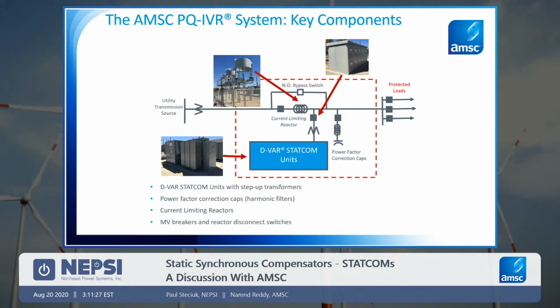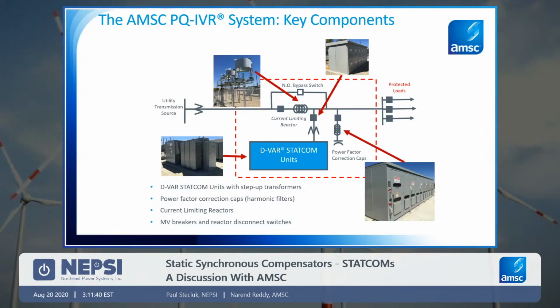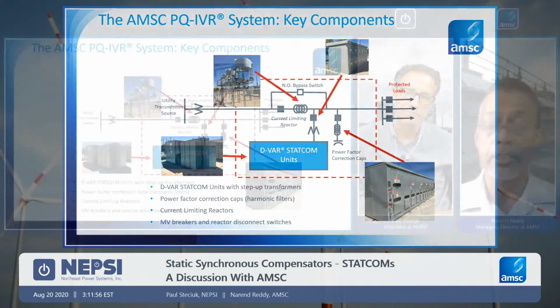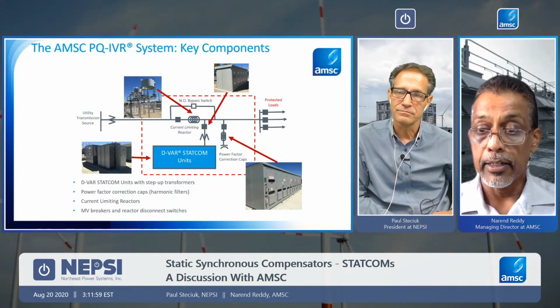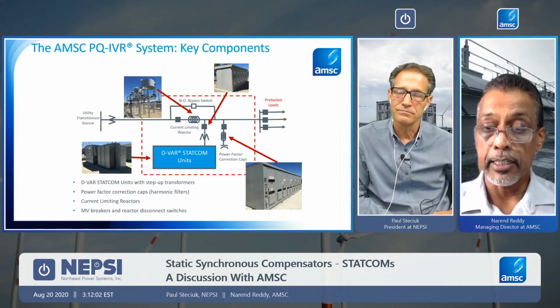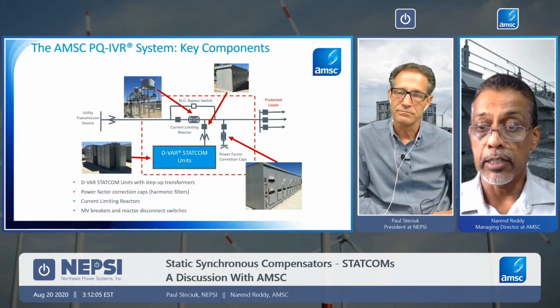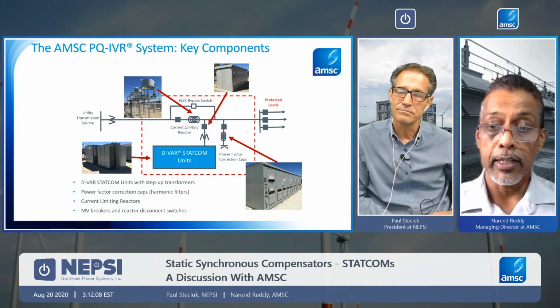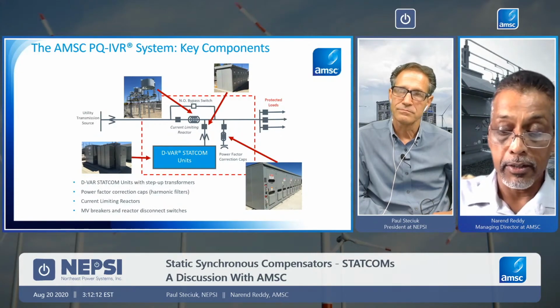So this is a picture of the dvar STATCOM units. You're seeing one unit, but typically that could be as many as 10, 12, 4 megavar units at a single location. And of course, a lineup of power factor correction cap banks. And this is not a one-step cap bank. There usually have to be multiple steps involved. But also, a lot of these installations are all harmonic filters. So while we are addressing power factor of the facility to keep the voltages high, at the same time you are helping mitigate the harmonic impacts of the customer as well.